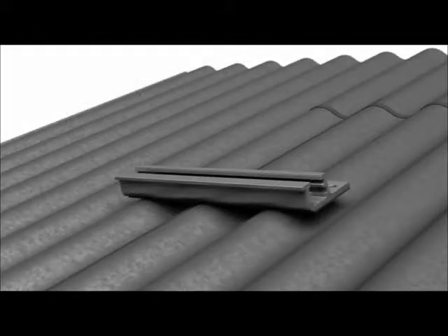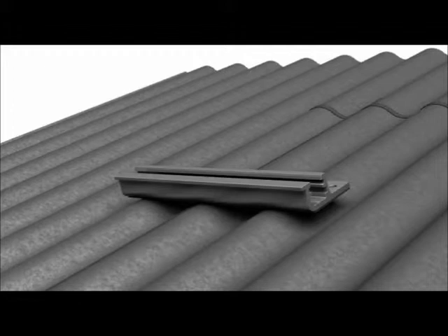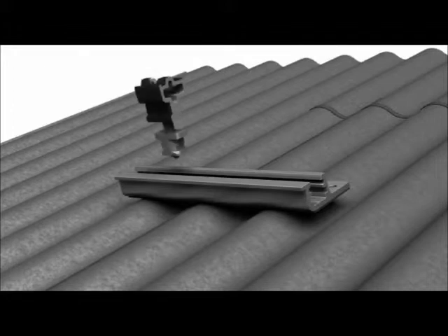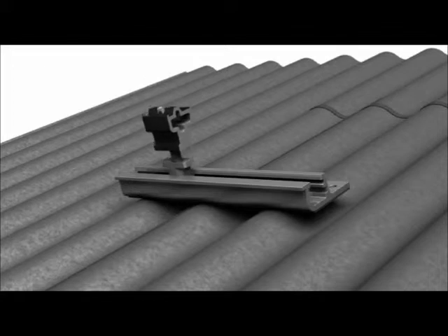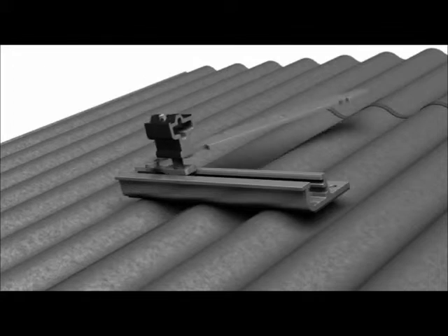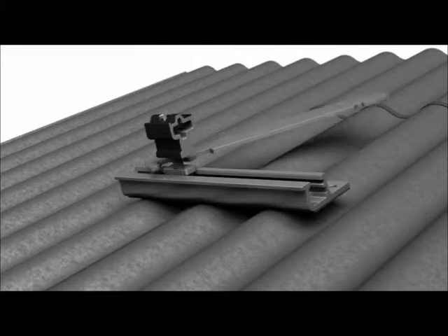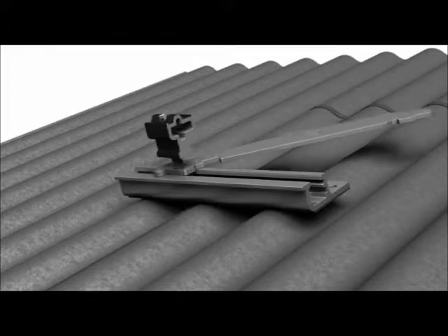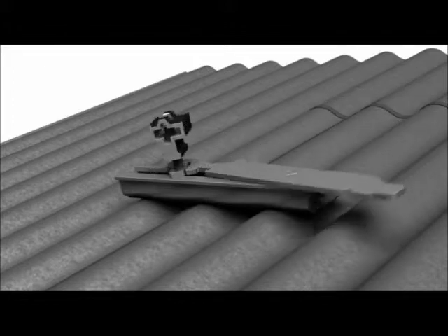Next, the first Camfoot is installed at the upper left corner of the array. To install a Camfoot, its Camnut is lowered into the channel of the Bigfoot. ZepSolar's Custom Flat Tool is then used to secure the Camfoot by rotating the Camnut 90 degrees in the clockwise direction.